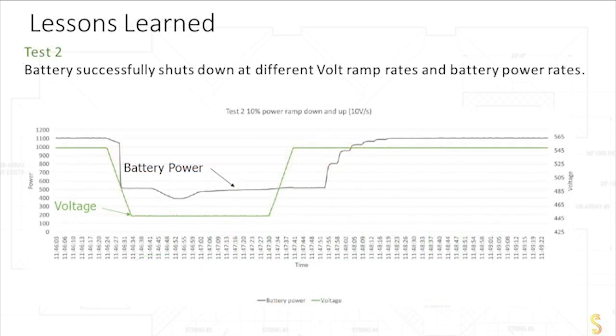Test number two shows what the battery does when the voltage is set differently. So test one shows how the inverter works under different operating conditions. Test number two shows what the battery does under different operating conditions. So what we're seeing here is the green line is the voltage that is being set by the inverter, and the darker line is the battery power. So if you start from left to right, you'll see where the green line suddenly drops. And it drops rather quickly, and the battery responds just a moment later. As soon as the green line gets set down, the battery responds immediately. And pretty quickly the battery drops its power rating. So that's what we want to see from the battery. We want to see that the battery responds to changes in voltage.